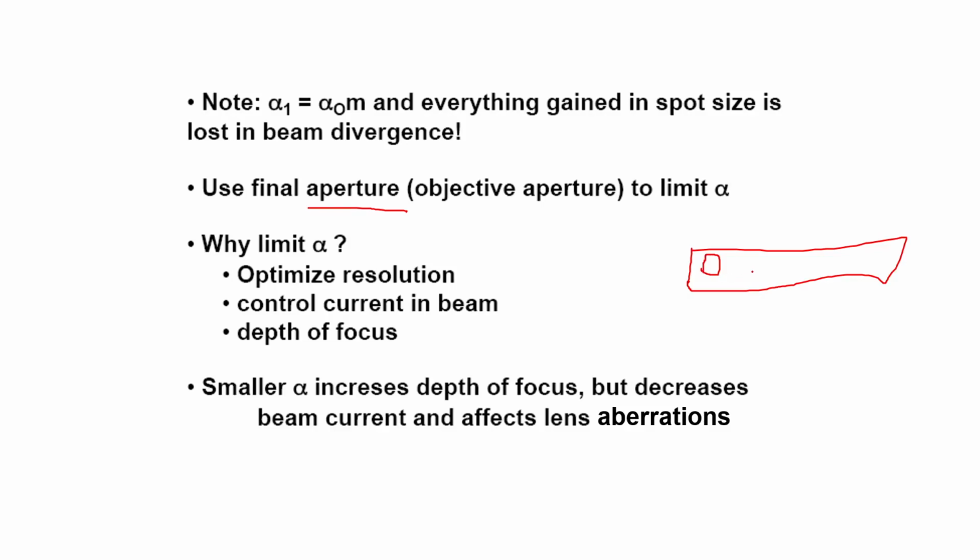Basically, you have a grid with different sizes of holes, and depending upon the image and the information you require, you put in a different kind of aperture. These are basically physical holes. Like this is all metallic, and these holes are hollow. So depending upon the information you require, you will put in a different kind of aperture.